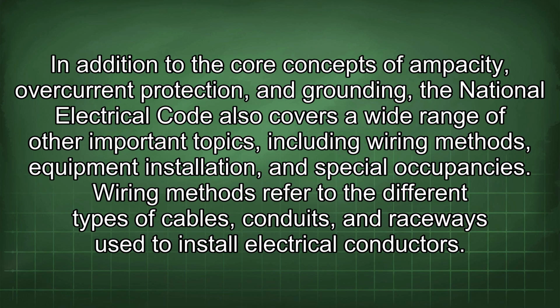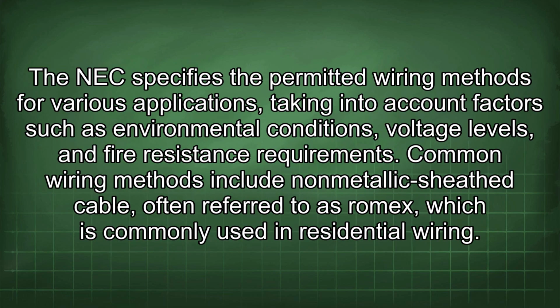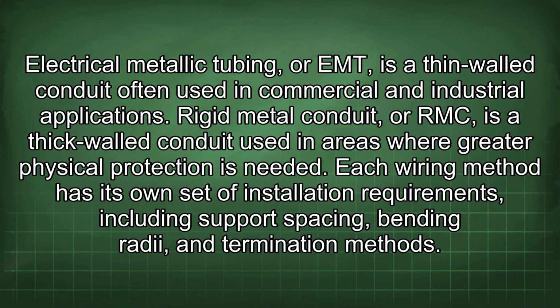Wiring methods refer to the different types of cables, conduits, and raceways used to install electrical conductors. The NEC specifies the permitted wiring methods for various applications, taking into account factors such as environmental conditions, voltage levels, and fire resistance requirements. Common wiring methods include non-metallic sheathed cable, often referred to as Romex, which is commonly used in residential wiring. Electrical metallic tubing, or EMT, is a thin-walled conduit often used in commercial and industrial applications.